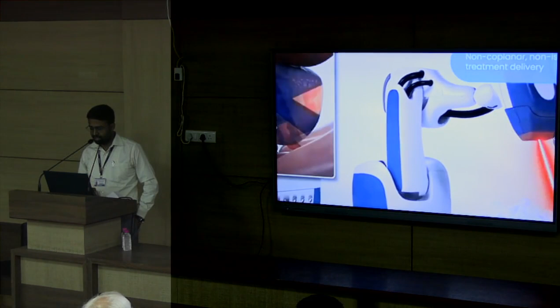Here the CyberKnife is rotating all around the patient to treat the cancer. So we have 1,400 beam angles, which is not available in any of the conventional linear accelerators, as I have mentioned. There are 2 X-ray systems available here, which can verify the patient positioning as well as the fiducial tracking. The fiducial tracking is done by the fiducial tracking algorithm, and once the algorithm has tracked, the patient is ready for the treatment. So it has a high throughput as well.